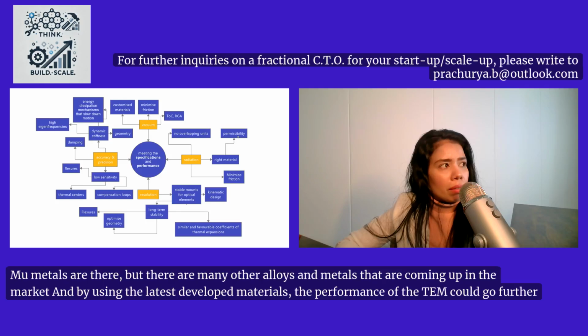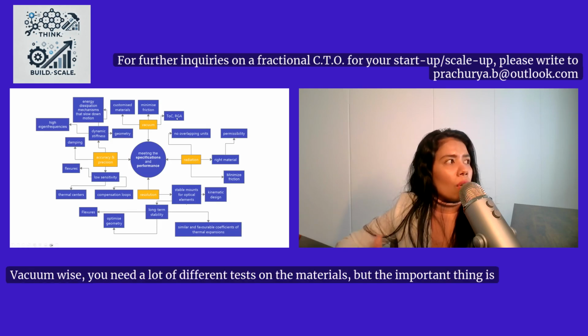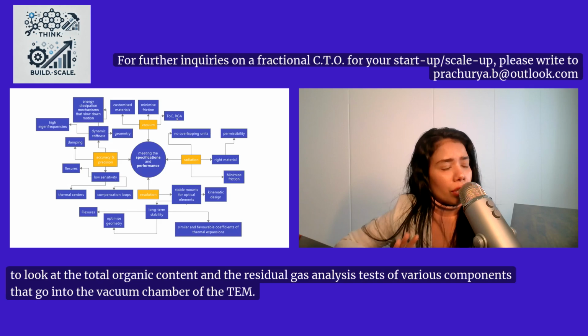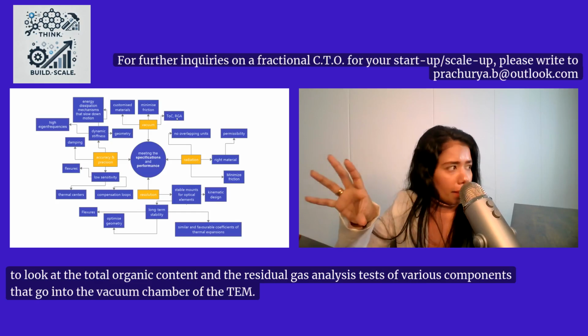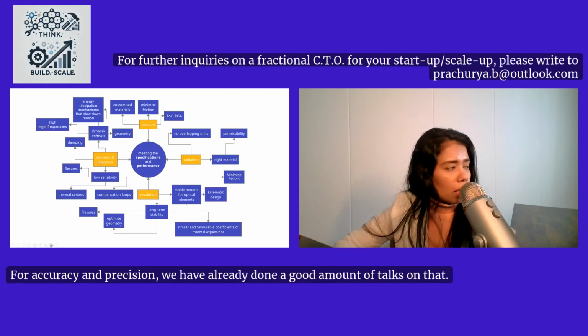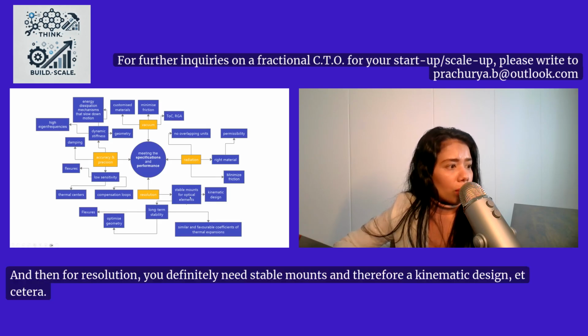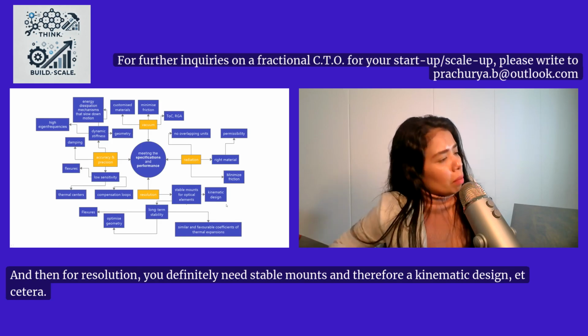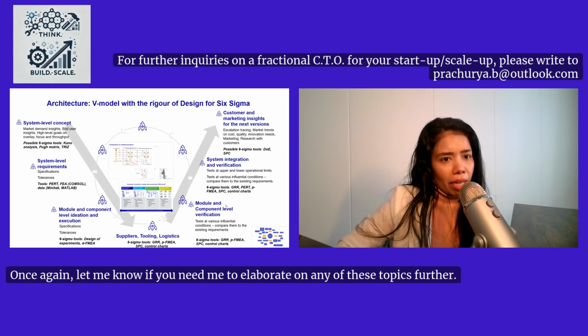Mu metals are there, but there are many other alloys and metals that are coming up in the market. By using the latest developed materials, the performance of the TEM could go further and further. Vacuum-wise, you need a lot of different tests on the materials, but the important thing is to look at the total organic content and the residual gas analysis tests of various components that go into the vacuum chamber of the TEM. For accuracy and precision, we have already done a good amount of talks on that. And for resolution, you definitely need stable mounts and therefore a kinematic design, etc. Once again, let me know if you need me to elaborate on any of these topics further.